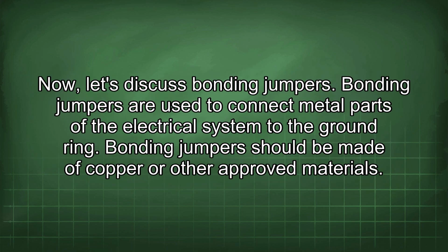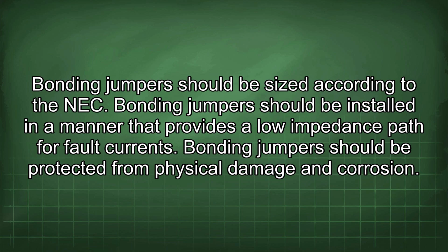Now let's discuss bonding jumpers. Bonding jumpers are used to connect metal parts of the electrical system to the ground ring. Bonding jumpers should be made of copper or other approved materials. Bonding jumpers should be sized according to the NEC. Bonding jumpers should be installed in a manner that provides a low impedance path for fault currents. Bonding jumpers should be protected from physical damage and corrosion.